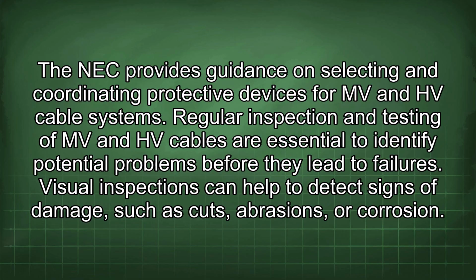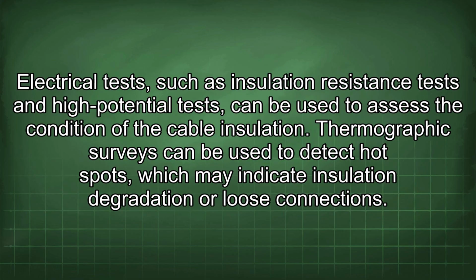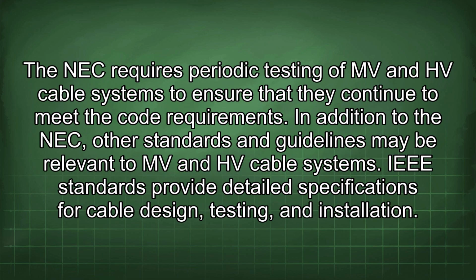Regular inspection and testing of MV and HV cables are essential to identify potential problems before they lead to failures. Visual inspections can help to detect signs of damage, such as cuts, abrasions, or corrosion. Electrical tests, such as insulation resistance tests and high potential tests, can be used to assess the condition of the cable insulation. Thermographic surveys can be used to detect hot spots, which may indicate insulation degradation or loose connections. The NEC requires periodic testing of MV and HV cable systems to ensure that they continue to meet the code requirements.